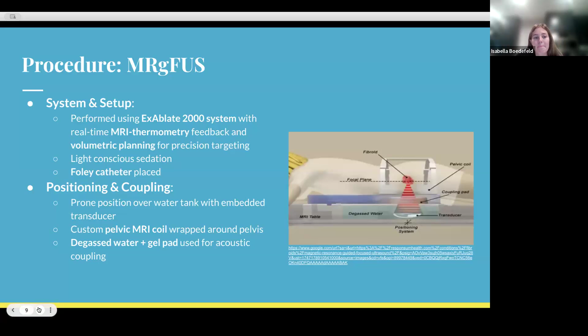So for pre-procedural planning, patients received a T2 weighted MRI in 3 planes to map their fibroids. And the ultrasound beam was about 5 millimeters wide and up to 35 millimeters long, with beam path checked for safety. And the procedure would start with low energy test sonications to confirm targeting. And these are followed by 12 to 24-second therapeutic pulses with cooling intervals that would last up to 90 seconds. And then these were adjusted in real time based on MRI thermal feedback.